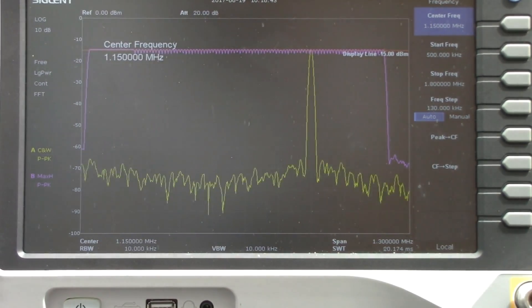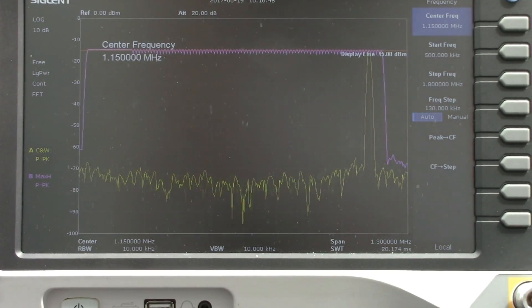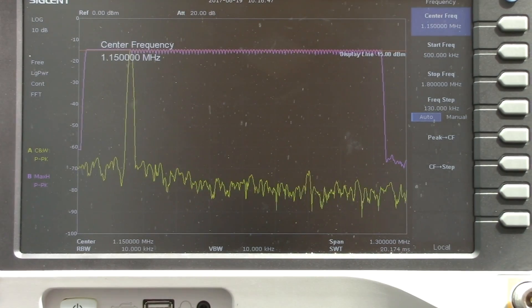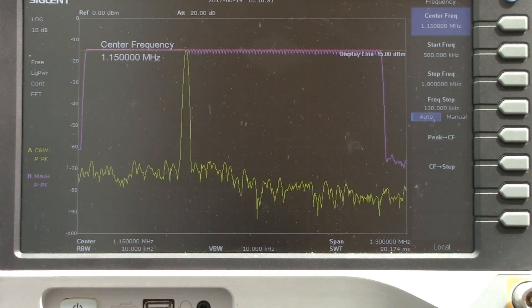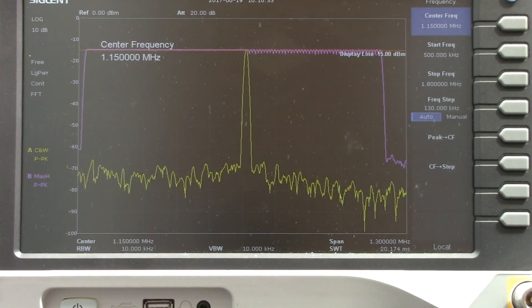And the uninterruptible power supply disconnected from mains, so battery powered. You'll see that the data does look quite similar if not identical as we continue to build up that trace. Again, yellow is going to be a clear write. It's going to overwrite every successive scan.